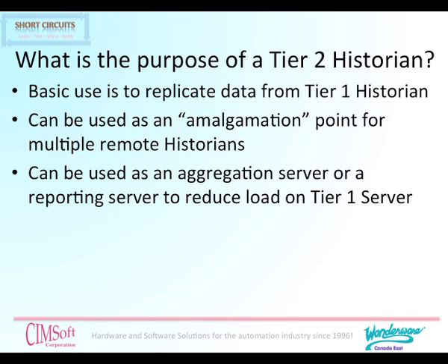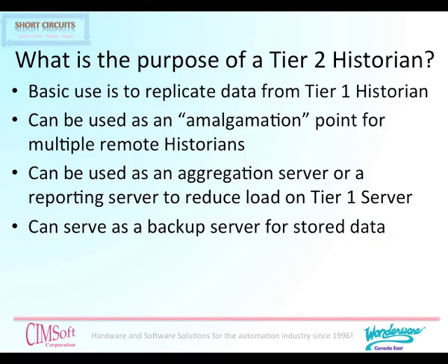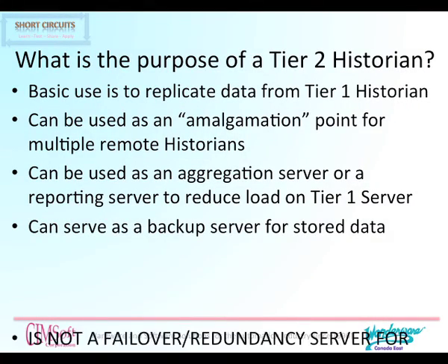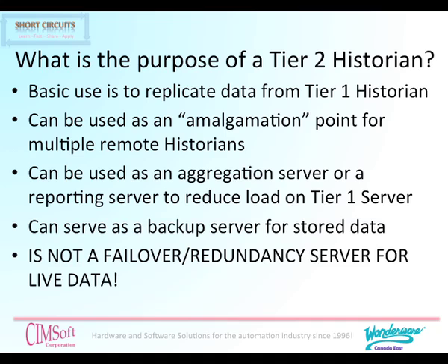So if a Tier 1 server was very busy collecting tens of thousands of data points, it would be wise to have those data points replicated back to a Tier 2 server, and that way all of the reporting requirements and the loading that they would create can be done on the Tier 2 server. It can also serve as a backup server for stored data, but it is important to note it is not a failover or redundancy server for live data. A failover redundancy server is a completely different type of server and has nothing to do with being a Tier 2 server.